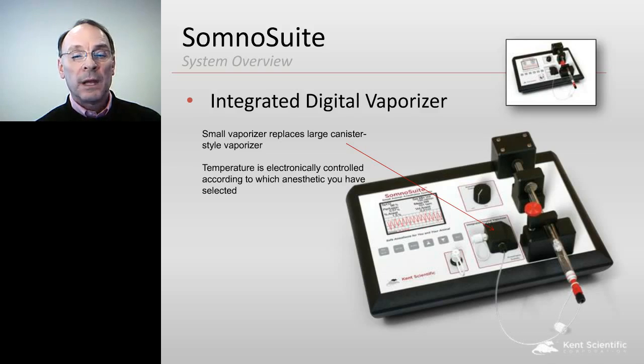And with a standard Somno Suite vaporizer, you can use compressed gas or room air. If you're using room air, it uses the internal pump. Otherwise, it uses the compressed gas on the back. We recommend that the compressed gas be anywhere from 5 to 10 psi. If you only have a high pressure source, we do have a small drop-down regulator that can be used on the back. And you can also use the compressed gas to drive the ventilator, as well as the room air to drive the ventilator.